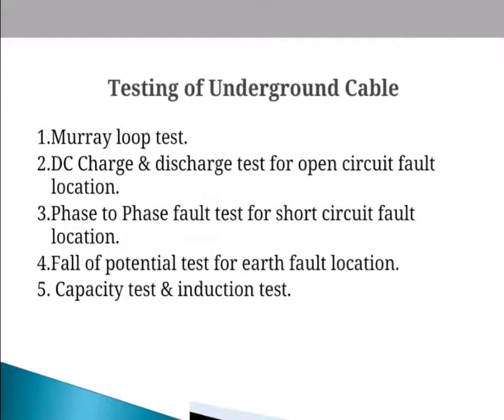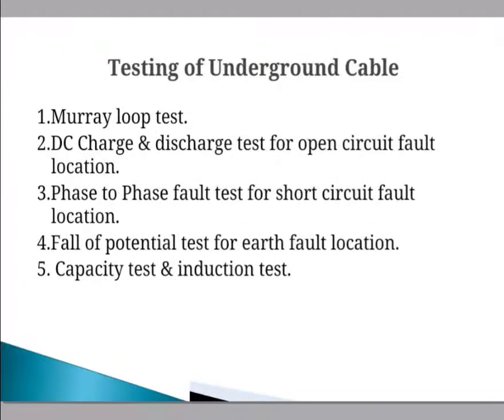For that purpose we test the underground cable with the help of the Murray loop test, the DC charge and DC discharge test for open circuit fault location, the phase-to-phase fault test for short circuit fault location, the fall of potential test for earth fault location, and lastly the capacity test and induction test in order to find the fault location of the cable. Then we will discuss in detail the different tests carried out on the underground cable.